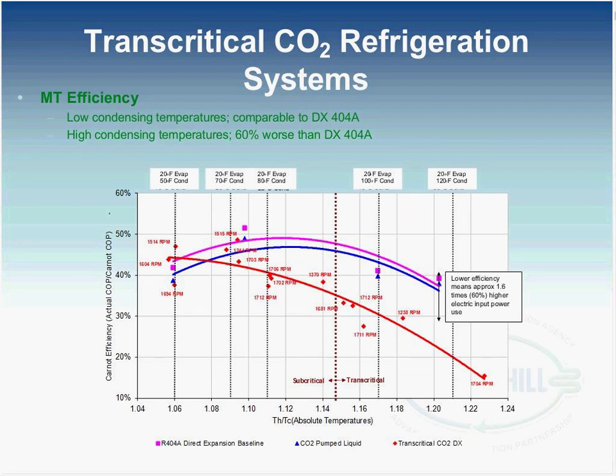I'm going to give a little bit of an overview of how these systems compare to more traditional systems that are used in supermarkets, or even some of the advanced refrigeration systems. We're not going to get too much into how a transcritical system works so much as how it operates. Here's a comparison of a 404A direct expansion system and a CO2 secondary or liquid recirc pump system, along with a transcritical system. You have the purple curve representing 404A, the blue curve representing a secondary CO2 system, and the red curve representing the cascade or transcritical system. They're operating around 20 degrees evaporator temperature and between 50 and 120 degrees condensing or gas cooling.